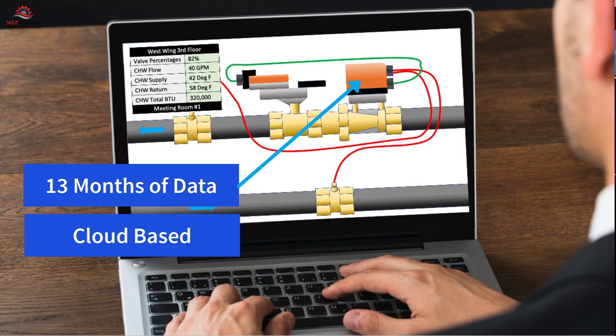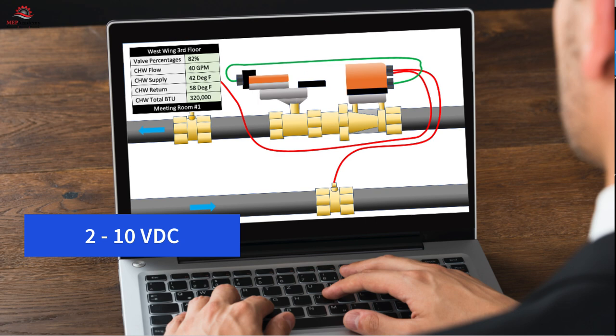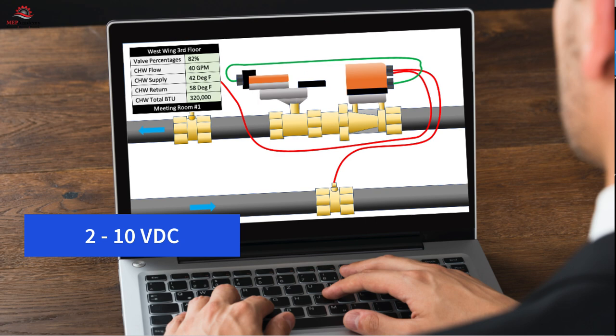The control range signal is set at the default of 2 to 10 VDC. If we look at the chilled water system serving a building, its purpose is to remove heat using as little energy as possible. This requires that the chilled water carry as much heat as possible within each volume of water passing through the coil.